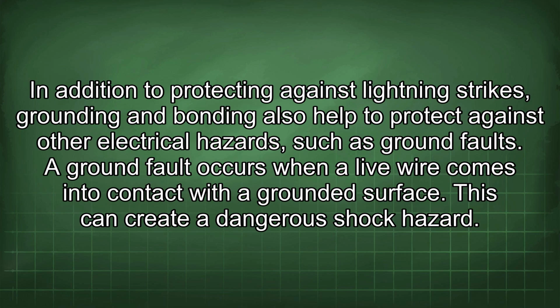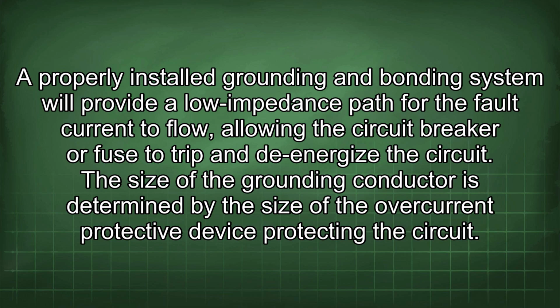In addition to protecting against lightning strikes, grounding and bonding also help to protect against other electrical hazards, such as ground faults. A ground fault occurs when a live wire comes into contact with a grounded surface. This can create a dangerous shock hazard. A properly installed grounding and bonding system will provide a low impedance path for the fault current to flow, allowing the circuit breaker or fuse to trip and de-energize the circuit.